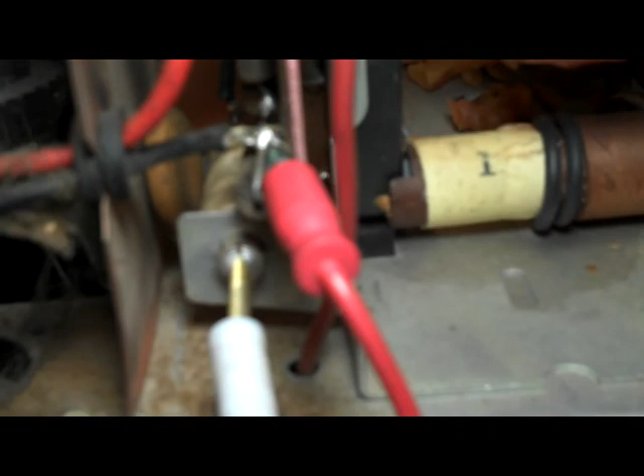Upon a close visual inspection of the capacitor that I suspected could be bad, I found that one of the leads is broken off. It's not even connected. I don't know if you can see this in the camera here, but this is the capacitor right here. And like I said, the location is not the best to try and film something, but I don't know if you can see that lead right there. So this capacitor is just kind of hanging on here by one lead. And that would explain a lot of the problems.